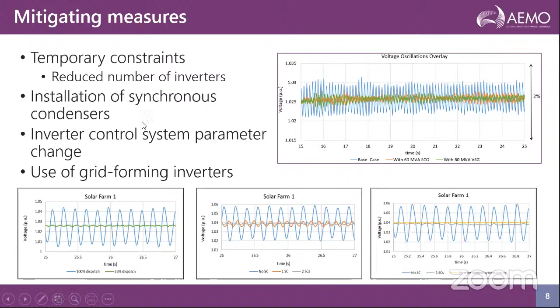The other option is to use grid forming inverters. And the figure on the top right shows that if you have grid forming inverters, that can also provide you system strength, and it can help to stabilize the voltage oscillation which you would see following a disturbance. So not only one, there are quite a few options available to address the system strength issue. Okay, something is popping up here. Should be okay. So let's go into the synchronous condenser environment.